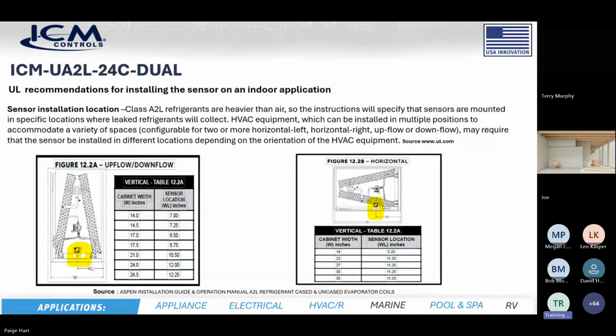And you see in these diagrams, they're showing you that it can be mounted so many inches away from the sidewall, so many inches up. So generally you're looking in the path of the airflow, right about midsection, maybe above the drain pan, not too close to the drain pan because you don't want water to get on it, but somewhere in that vicinity, right in the airstream. And on this one here, you see it's on the side, where again, remember, the refrigerant is heavier than air, so gravity's gonna bring that refrigerant down, and you want it somewhere around the middle of the coil where the refrigerant's going to collect.